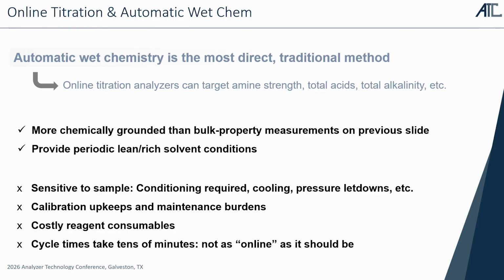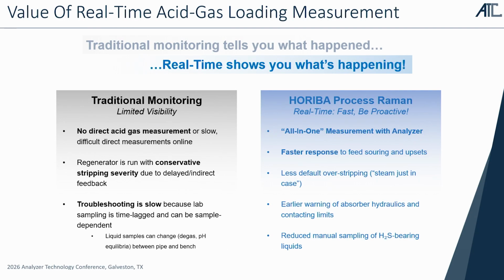There's a ton of sample conditioning that has to happen before you can bring it into an online titration analyzer. You have to temperature control it. You have to relieve pressure. These are very sensitive to how the sample meets the analyzer. Calibration upkeep, there's lots of costly reagents and consumables. And cycle times can take tens of minutes, and that's not really online at that point, right?